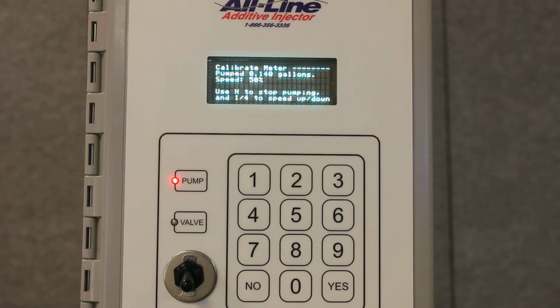So we just have to wait for it to hit the gallon mark, and we'll stop it there. I'm filling the jug: 0.4 gallons, 0.5 gallons. You can use any size of container you wish; I just find it easier to find a 1 gallon container than just about anything else. 0.8, 0.9, and I'm going to close the ball valve at exactly a gallon.